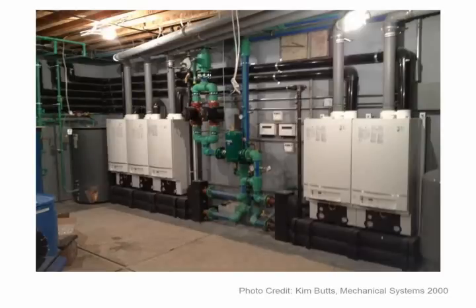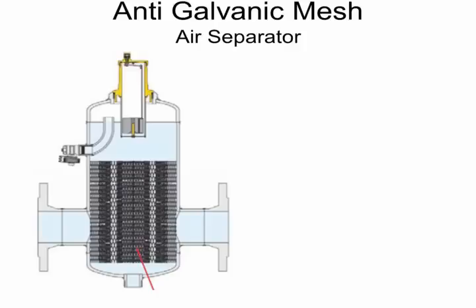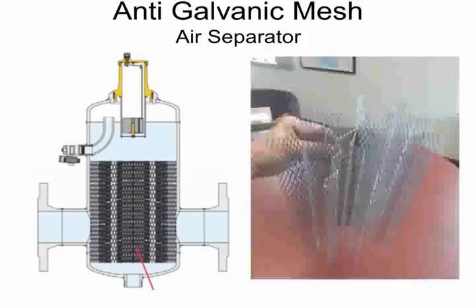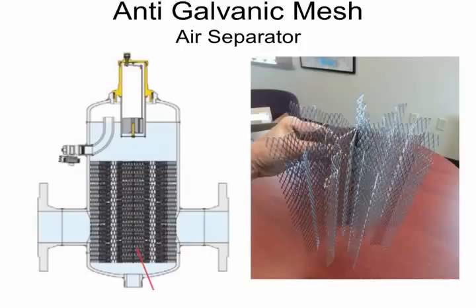But the thing to point out is the piping. This is, I believe, aquatherm piping. It's plastic piping. So what does that do with corrosion? Well, it does help the issue of corrosion. You don't have any effects of galvanic attack from, say, flow from this air separator to these pumps or to the boiler. You have basically an insulation going on. Now, does that stop corrosion from happening galvanically? No. Within each component itself, you could get corrosion amongst the different materials within that component. So as an example, if you took our air separator that you just saw in that last slide and looked at the inside, well, kind of the working end, if you will, the business end of an air separator is its mesh.